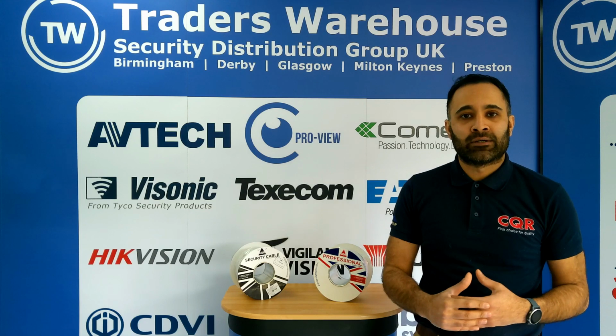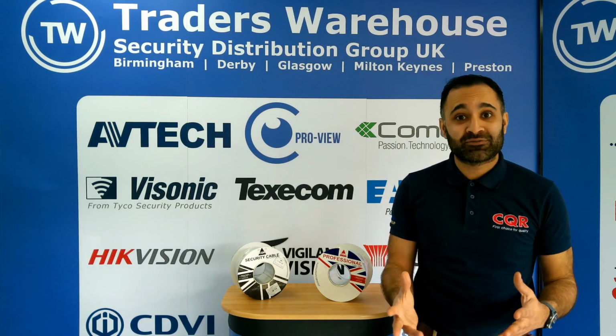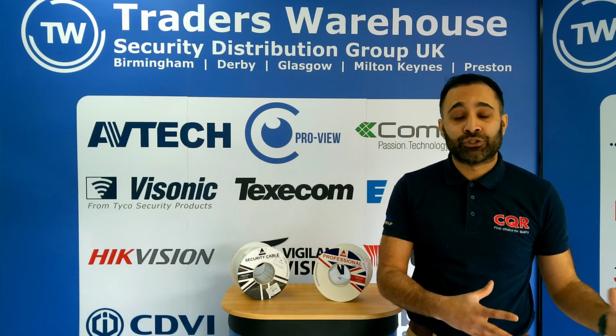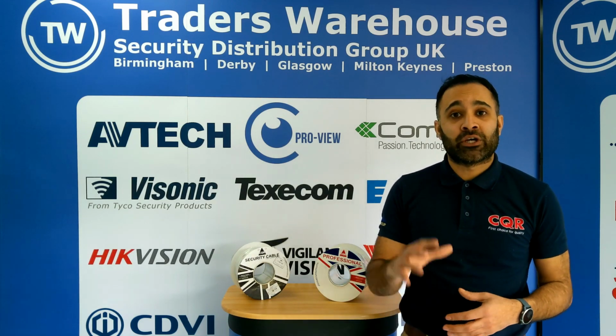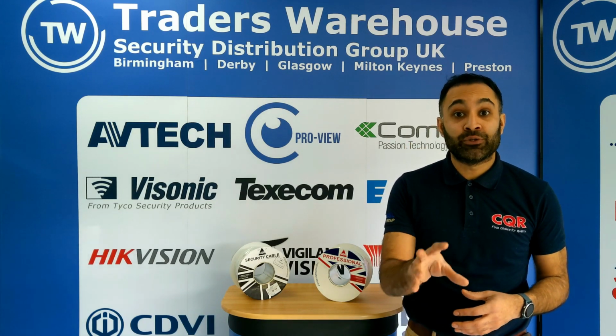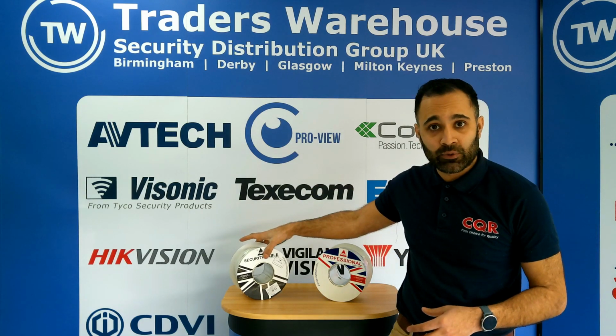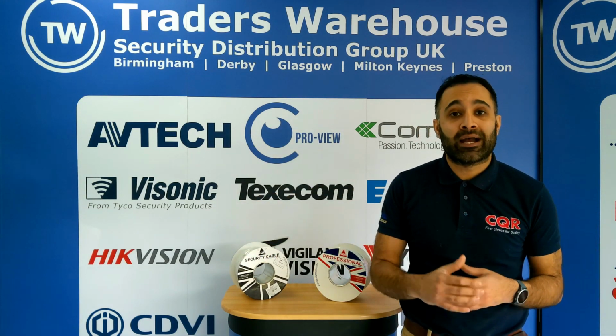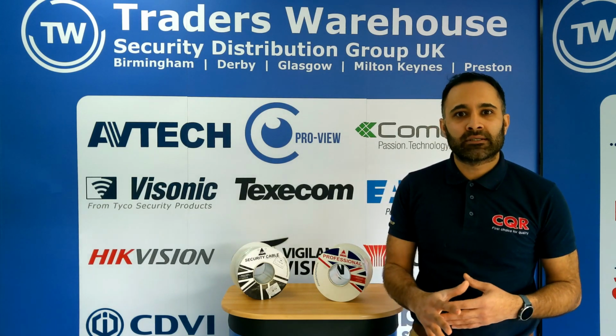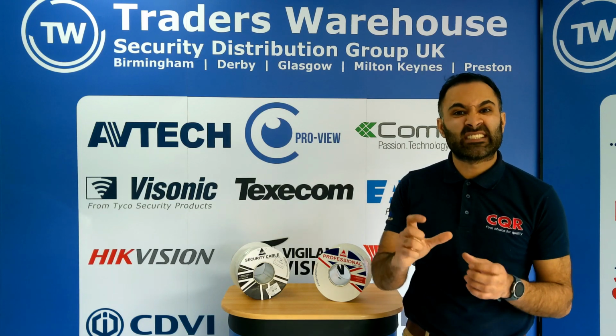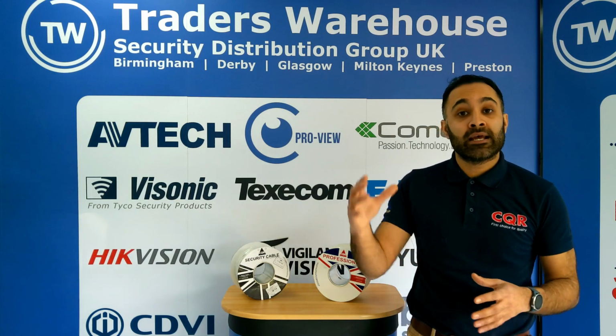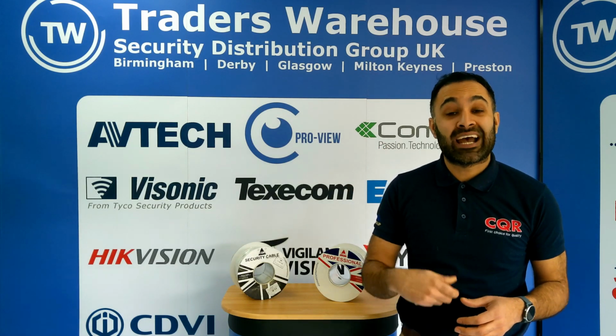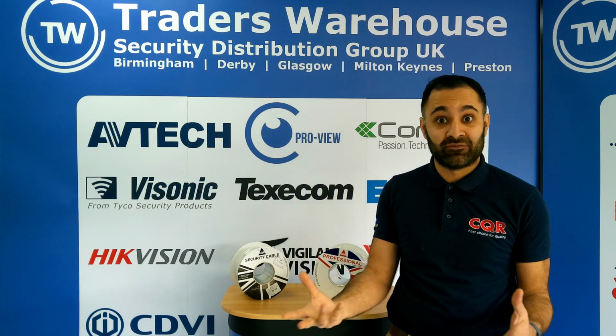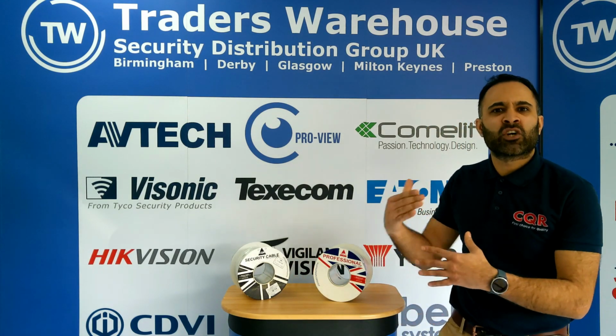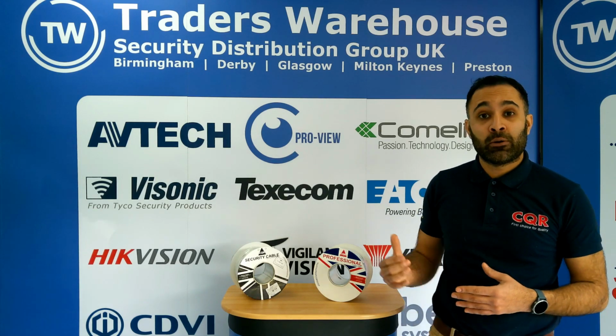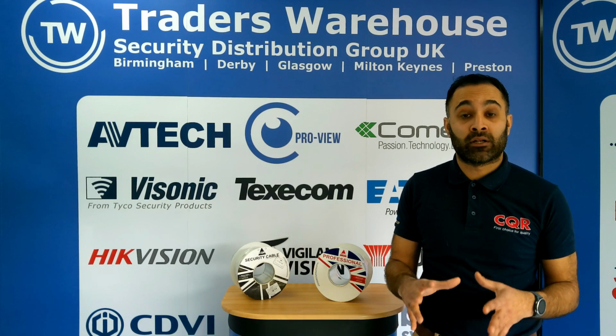So firstly, I'd like to point out there was a standard change, BS4737 standard, which was introduced in 2016. The point of this standard was to identify what different types of cable you use. We have CCA cable here, and that is a type 3 cable as per the standard. One of the main reasons that makes it a type 3 cable is its resistance value. So CCA cable per the standard needs to be less than 155 ohms and more than 100 ohms per kilometre in resistance. Copper cable, that's a type 2 or type 1 depending on the sheathing that is used, but it needs to be less than 100 ohms per kilometre.